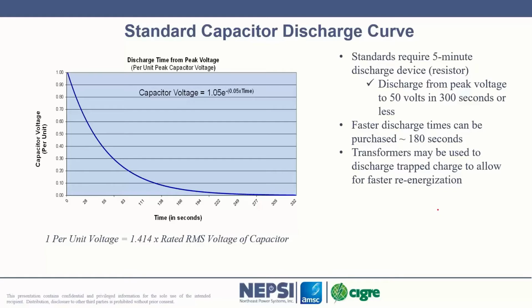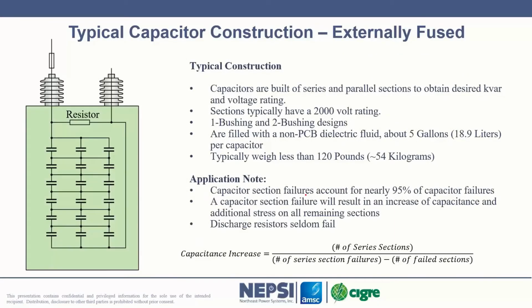They all come with discharge resistors. Typically, it's a 5-minute discharge. They'll take the capacitor from peak voltage and drop it down to 50 volts or less in 5 minutes, 300 seconds. So that's pretty much standard. This is an internal shot of an externally fused capacitor. Here's that resistor here.